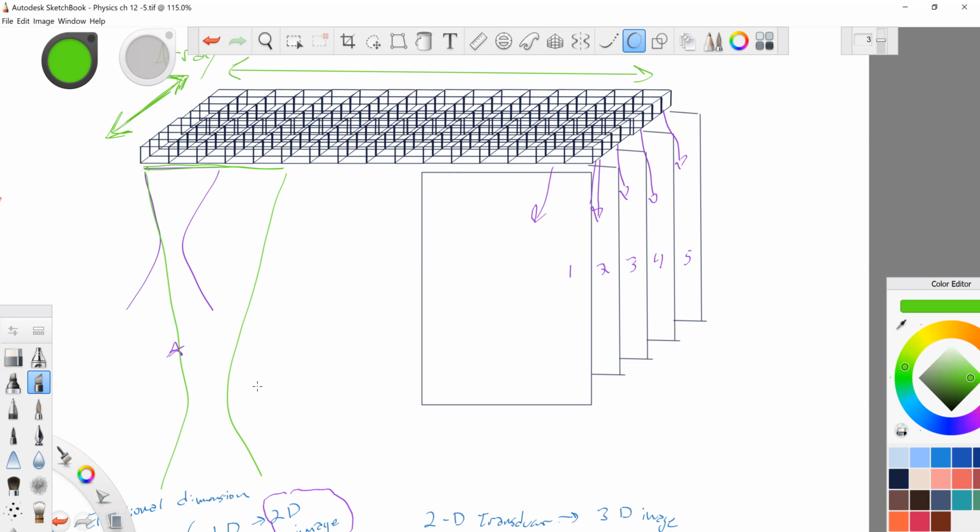So each pulse, each focal point can have, if we're talking about dynamic aperture on the way out, the actual creation of the sound beam, you could only have a dynamic aperture if you have multiple focal points. Each focal point will be phased differently because phasing creates different focal points, but you might as well take advantage of the fact that a natural focus for a deeper structure could benefit from a larger aperture.